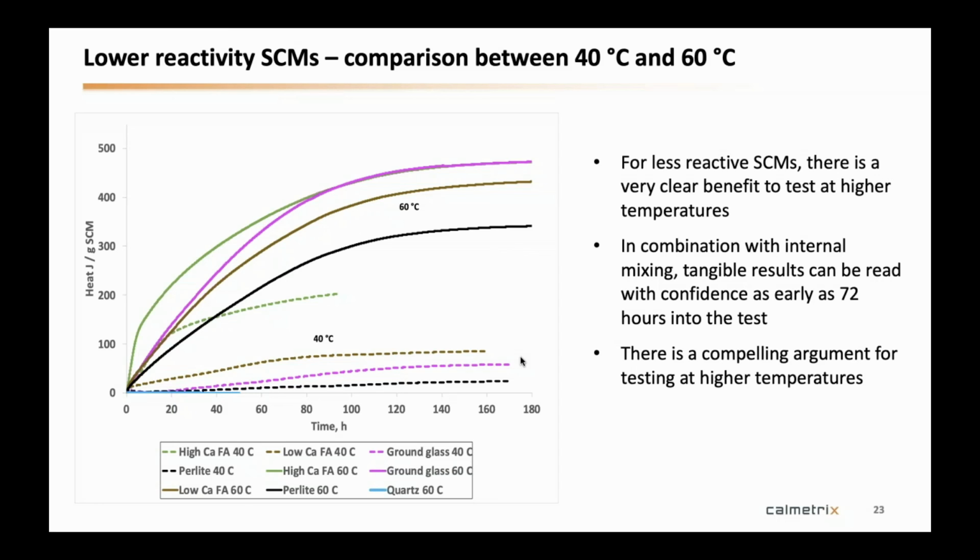Yeah, I think, Mark, probably what Abdul is referring to is if you're doing a test inside of the calorimeter at 40 degrees C and your ambient in the lab is 23 degrees C, is there any reason to increase or decrease the differential between the ambient temperature and the calorimeter to maximize? No.